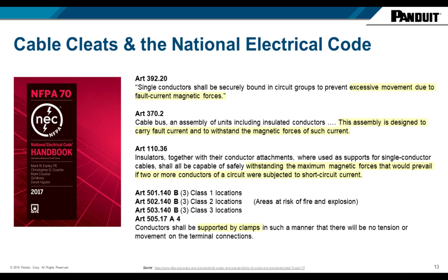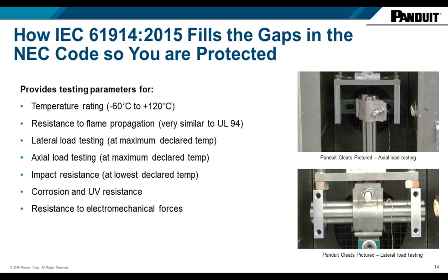Looking at the NEC — the National Electrical Code in North America — many people design and specify installations according to it. Article 392.20 asks for all single conductors to be securely bound in circuit groups to prevent excessive movement due to fault current magnetic forces. It recognizes this phenomenon, but what it doesn't do is tell you how to restrain those forces. That's where IEC 61914 comes into play.